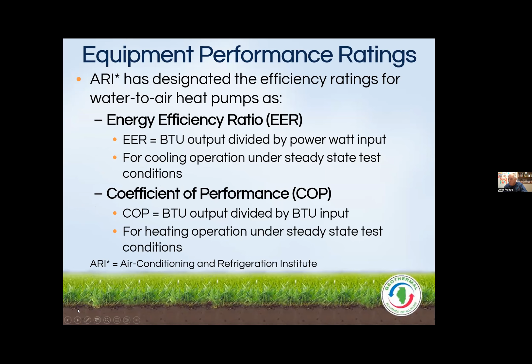Why don't we use SEER for geothermal? We don't, for one reason: underground knows no season. It's the same year round, remember we're right in the sweet spot. So we use energy efficiency ratio for cooling. And for heating, we rate on COP, coefficient of performance. That's a complicated term, but the higher the number on both, EER or COP, the higher the energy efficiency rating.